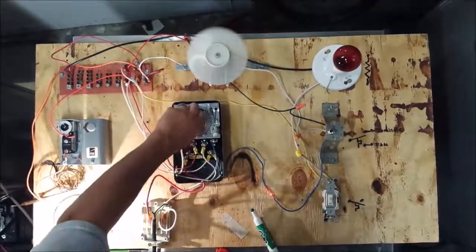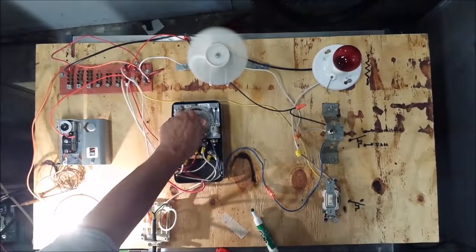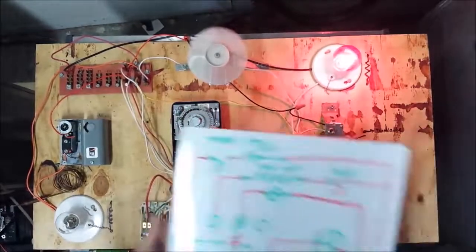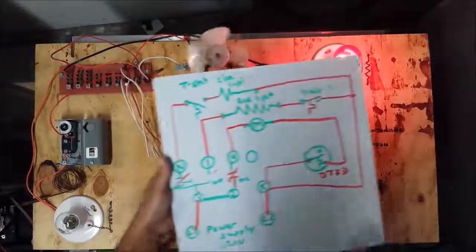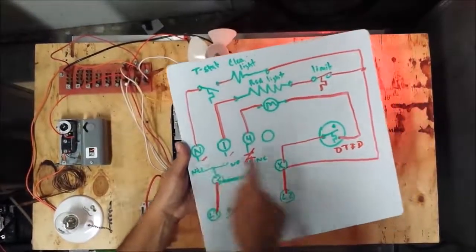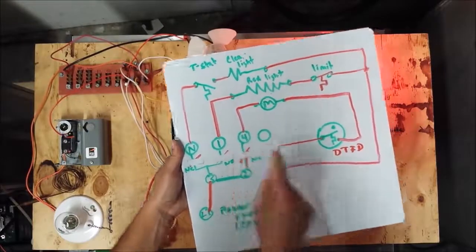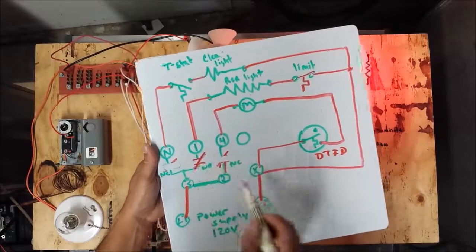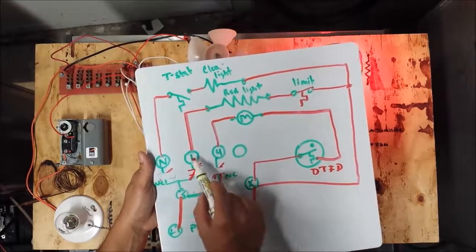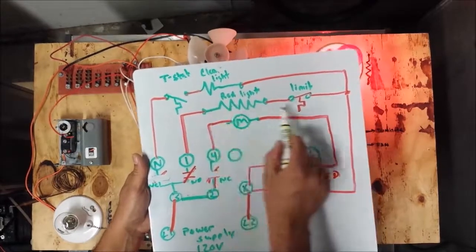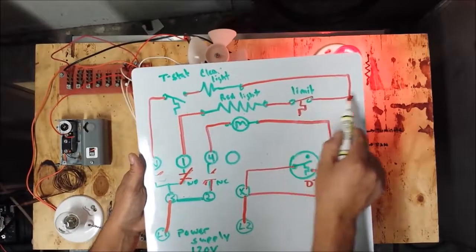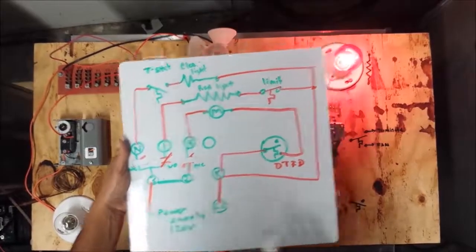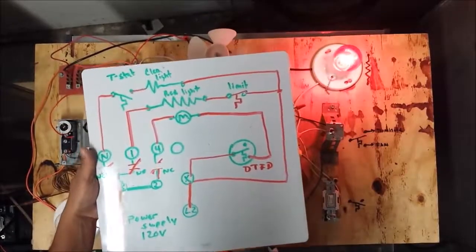By the way, this does it automatically. Okay, so what happened here now is our normally closed switches on our defrost clock have opened, and we have now closed our normally open switch, and that feeds this red light. The limit switch is closed. That comes back to L2, and we have a red light running, or a defrost heater running.